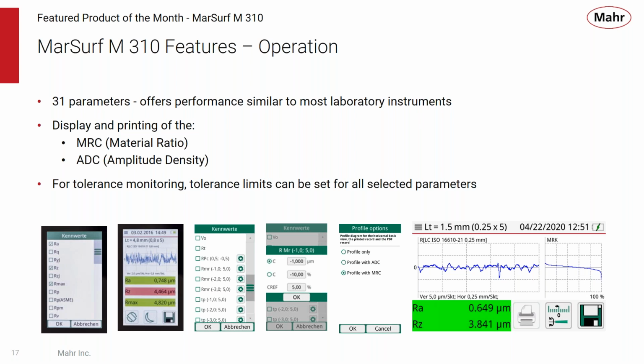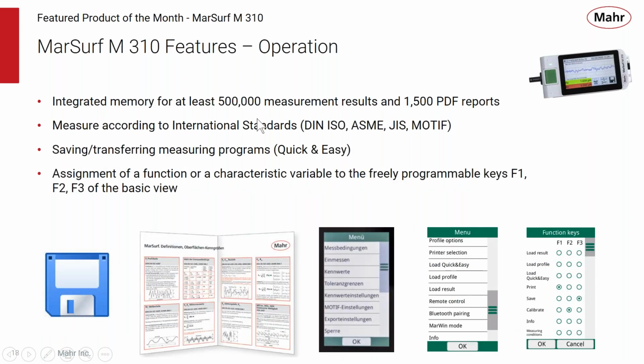And with tolerancing, there can be limits set, so you can monitor the parameters. You can get colors for the results, and it's a simple go no go method for the user to ensure that the part is good or bad. With the integrated memory, you can store at least 500,000 measurements and 1,500 PDF reports. All the measurements are done by international standards, whether they be DIN or ISO or ASME standards.